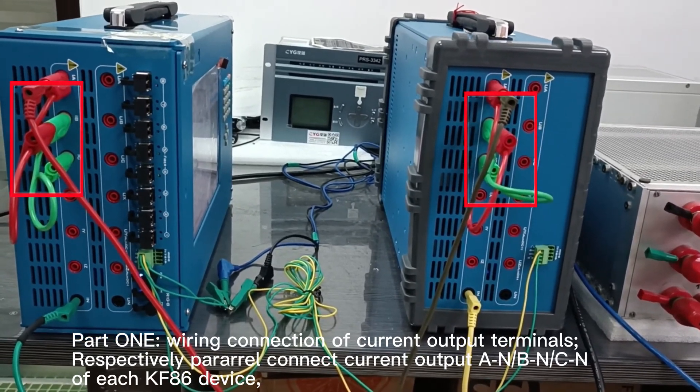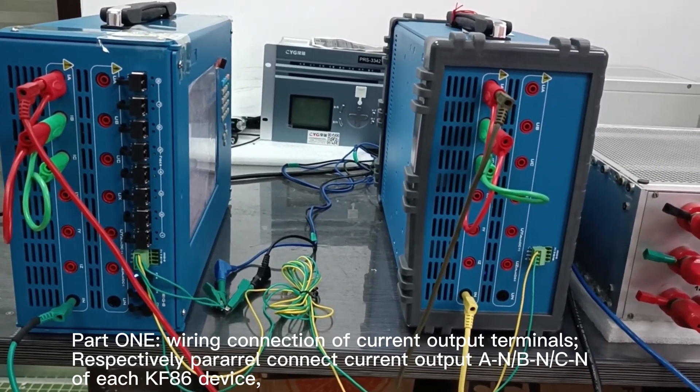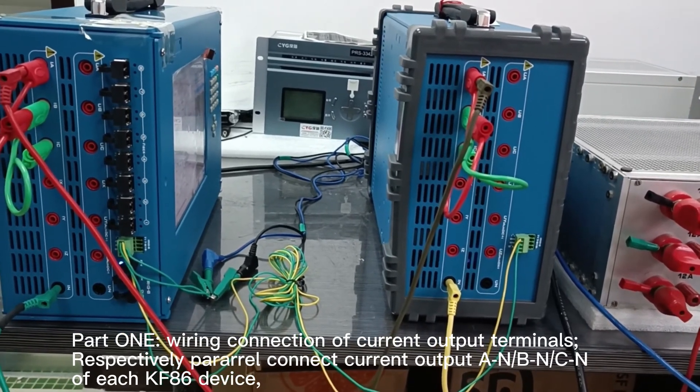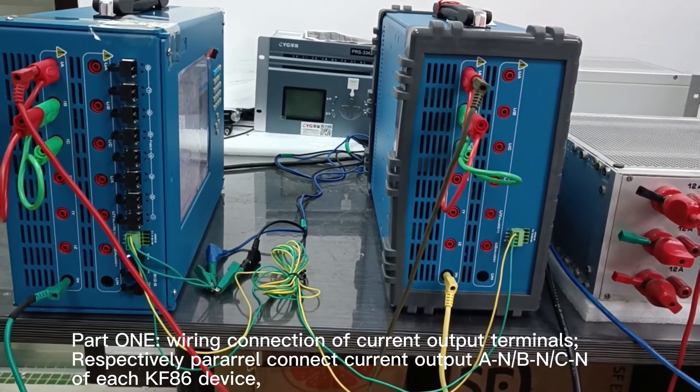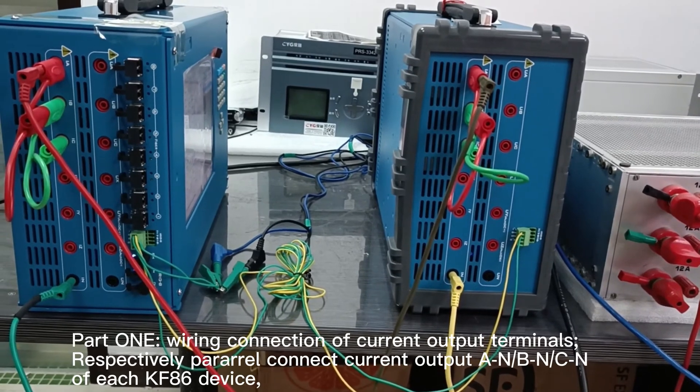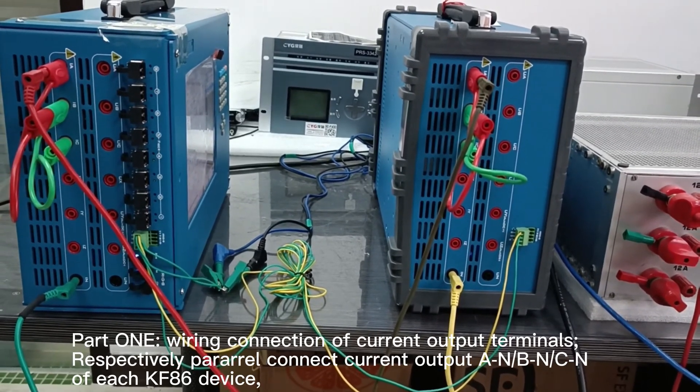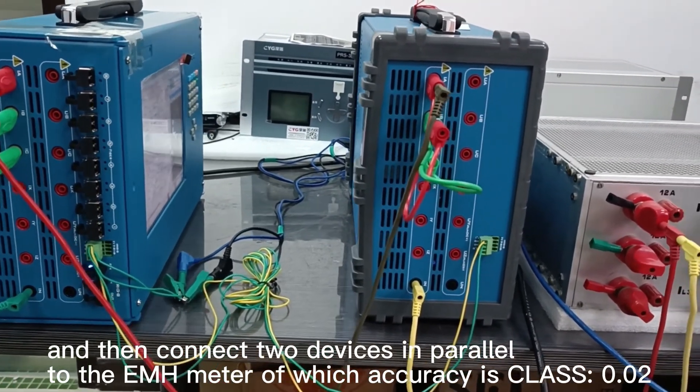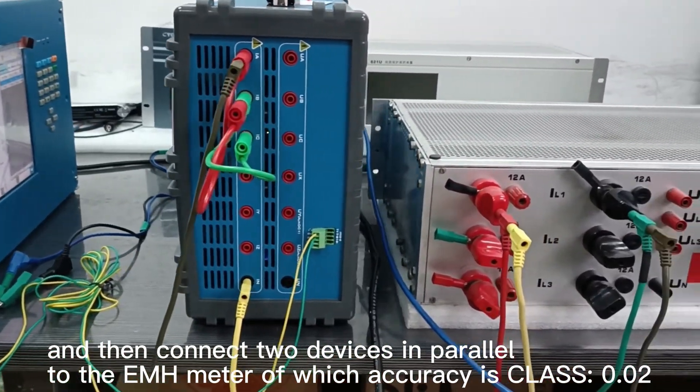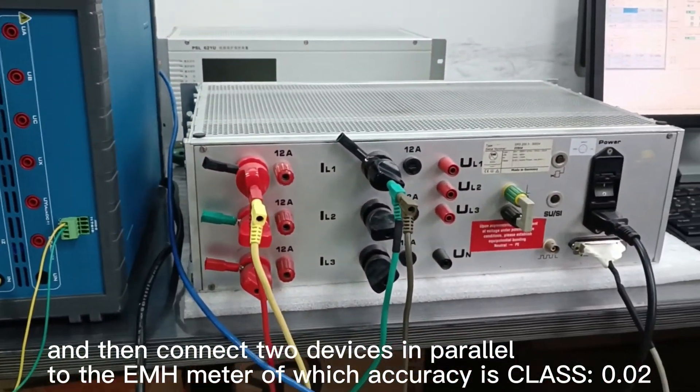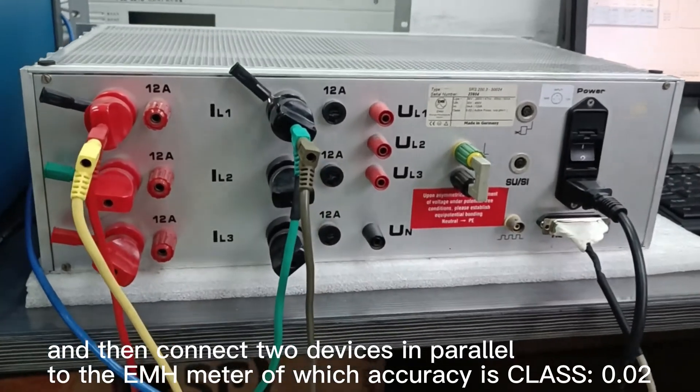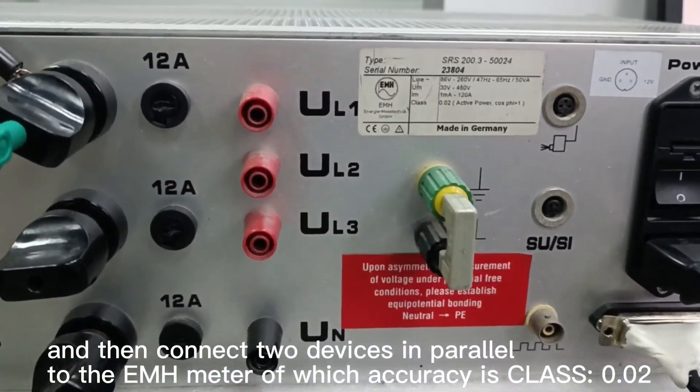Respectively, parallel connect current output A to neutral, B to neutral, C to neutral of each KF86 device, and then connect the two devices in parallel to the EMH meter which has accuracy class 0.02.